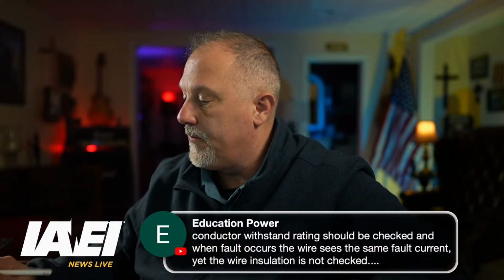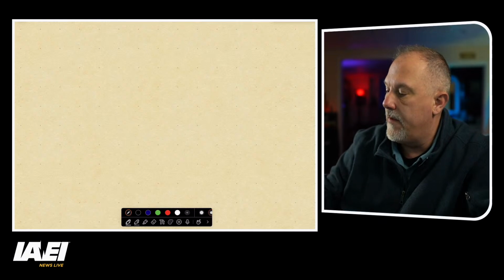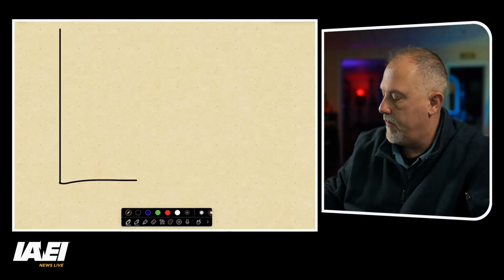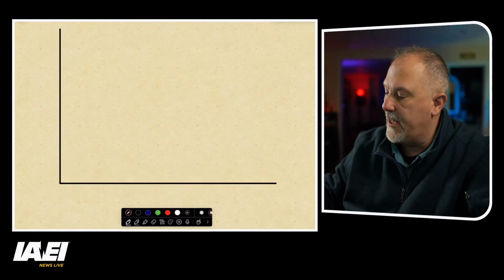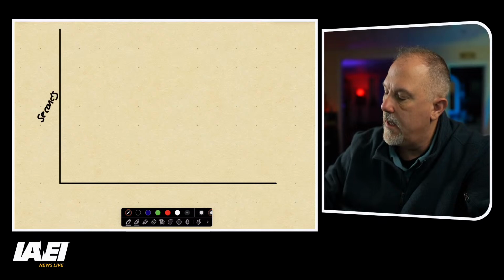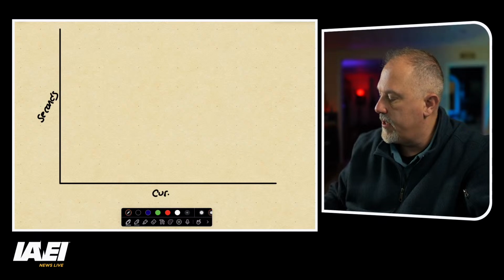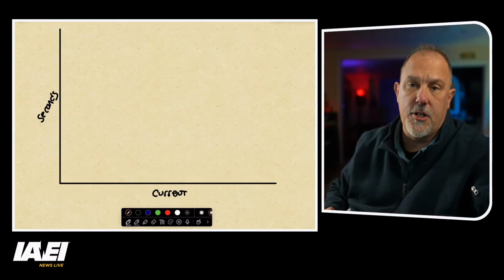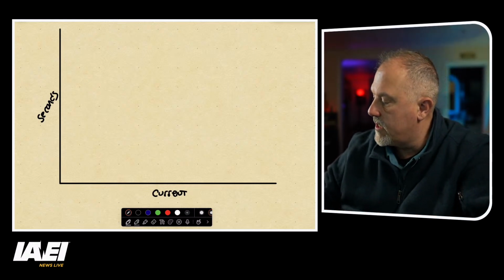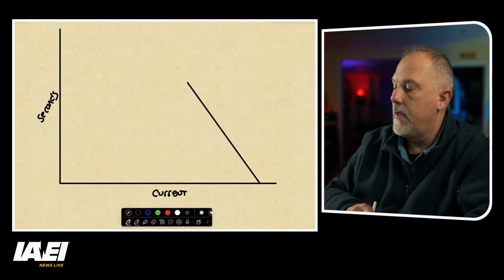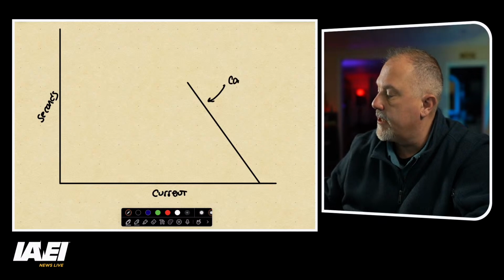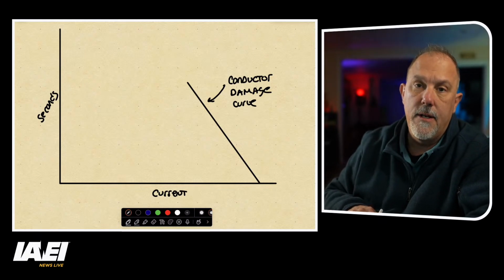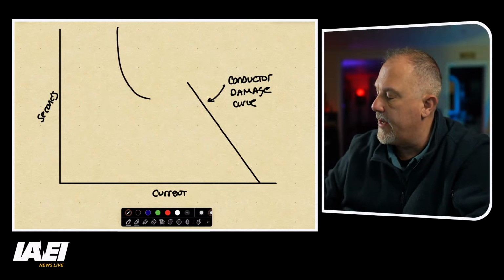If I had a time current characteristic curve, remember, on a TCC curve, we have seconds up the y-axis, and we have current here. The damage curve for a conductor looks something like this. Okay, and this is a conductor damage curve. And what we would typically do is plot a circuit breaker. Let's say we plotted a thermomagnetic circuit breaker.